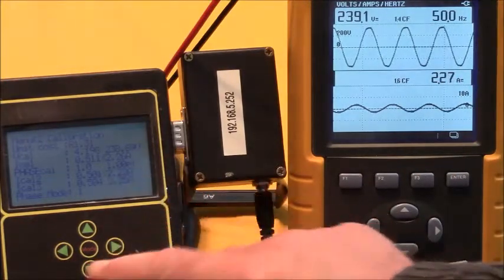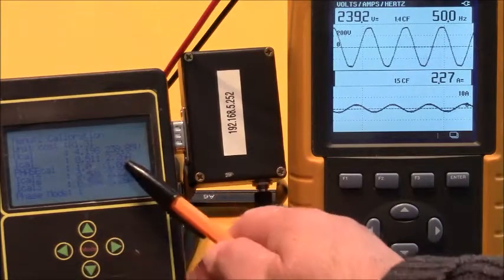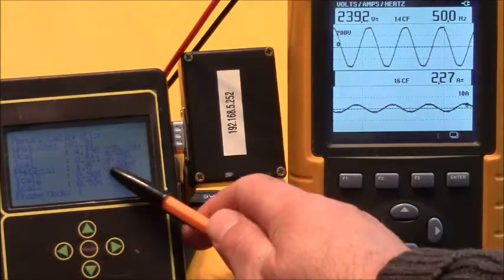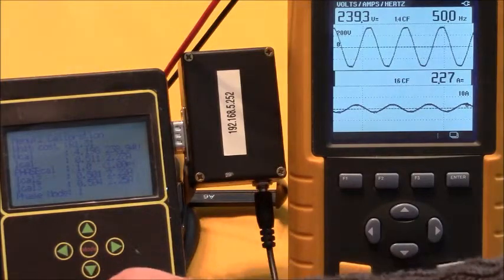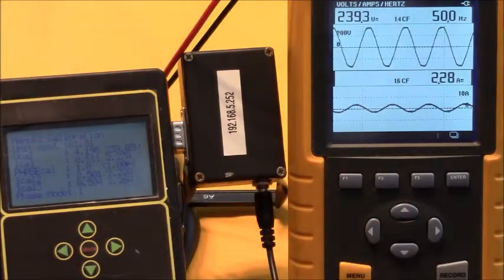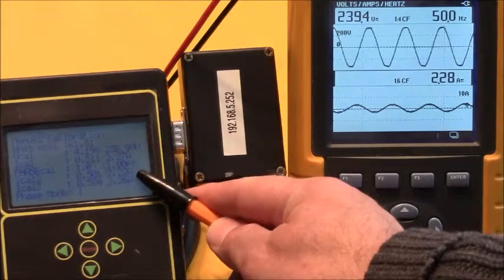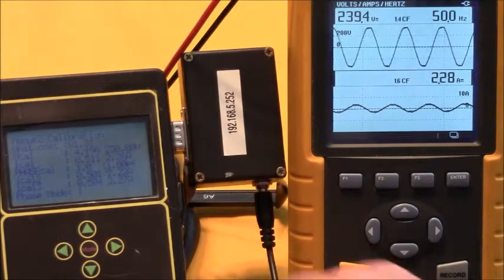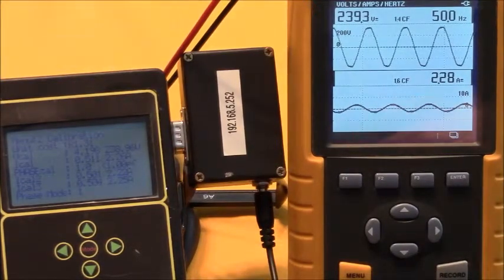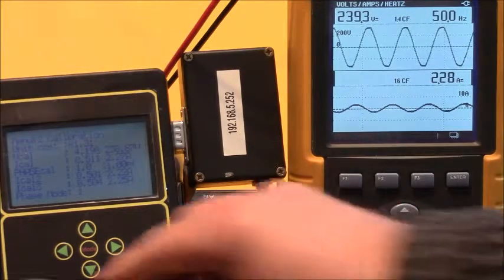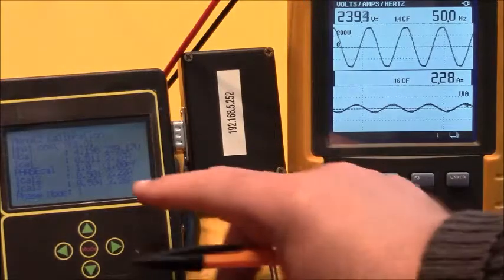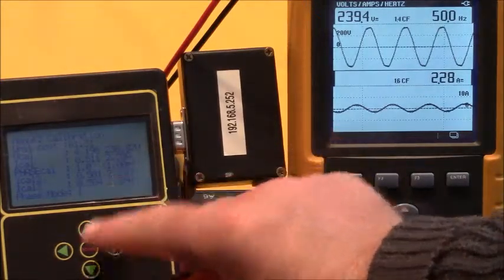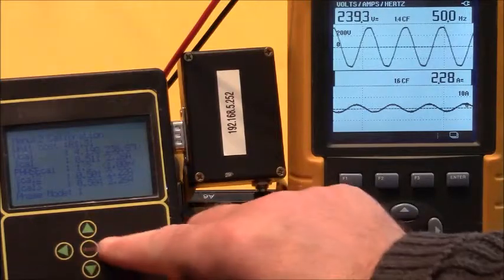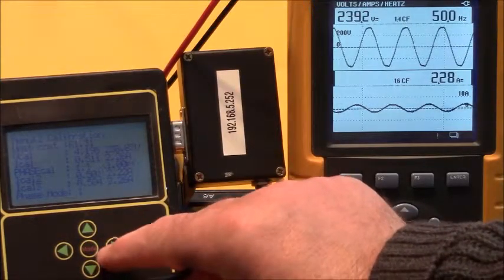Now the other two current sensors, the power factor, you generally don't have to do any calibration. The other two current sensors, number 2 and number 3, are all on the same AC wire, so you can actually just change those values to match the top one. There's very minimal tolerance in the actual current clamps, so it doesn't matter if you interchange these, they will record the same value. So I just want to push this value up. Sorry, wrong location. That's the power factor.